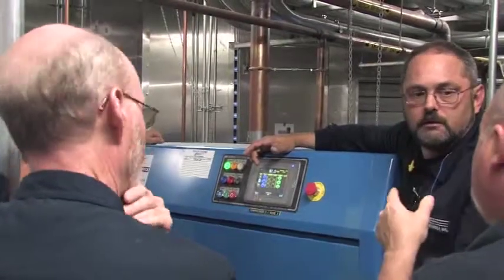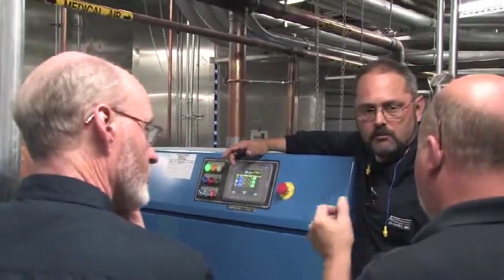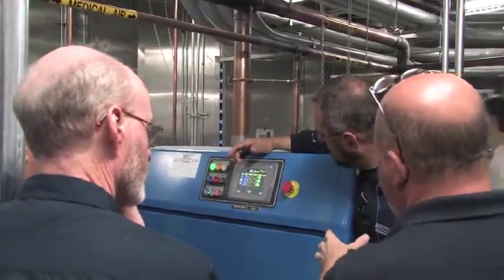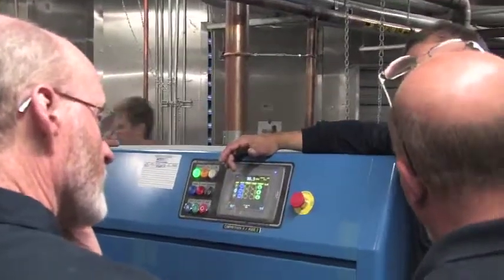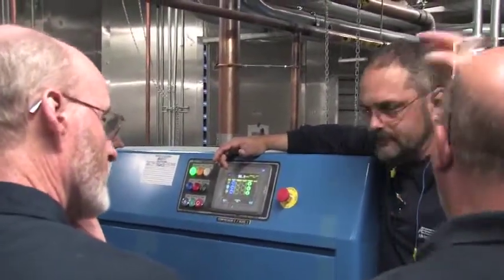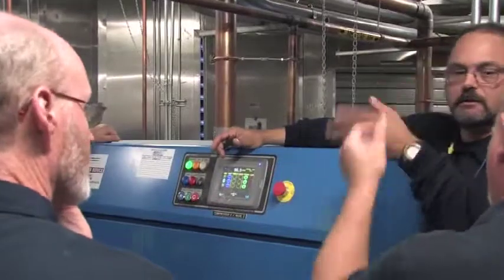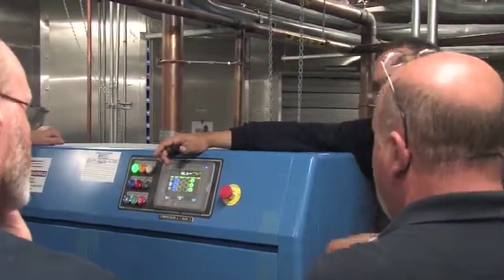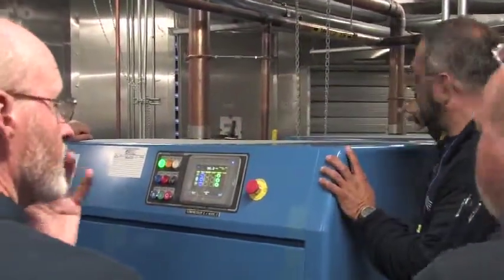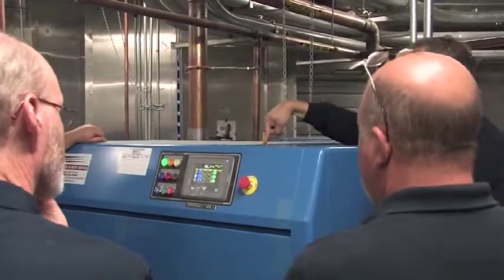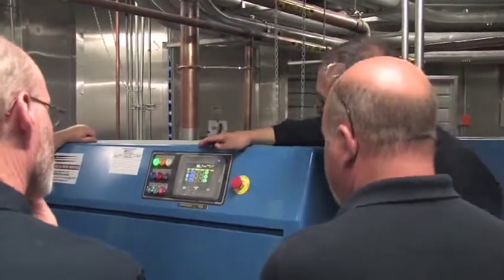Yes. So this will only go forward, it won't go backwards. If this is lead, you can't make number one lag. It goes lead, lag, standby. With 3 units, it always goes forward. Always lead, lag, standby, rotating through. So when that becomes lead, that's lag, this is standby, and so on and so forth.